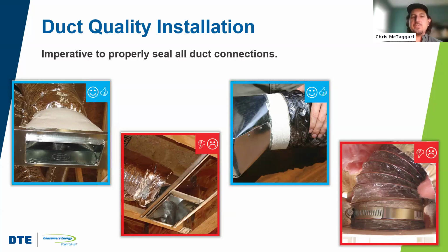then there is a more significant level of duct sealing that may be necessary in order to really achieve these rates. Ductwork is a fabricated product that has a lot of seams in it, and it can also be sensitive to getting cut or spliced, where the tightness is reduced over time. And so, there's a lot more that goes into proper duct sealing. Obviously sealing all the basic seams of the system are required, but also sealing the duct boots themselves. So the inside of boots and fittings should be sealed.